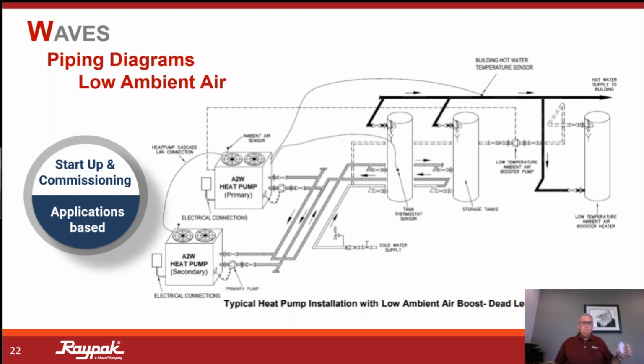Question, so as soon as it goes in low ambient temp, the 2 pumps on the main heat pump shut down? That's a fair question. We're going to talk about air next, but the refrigerant that is used in these heat pumps is R134. And it basically has an ambient air temperature minimum of 40 degrees. Otherwise, we potentially can need to do a defrost cycle. So anytime we're below 40 degrees ambient, you're really not going to get the production out of these units.